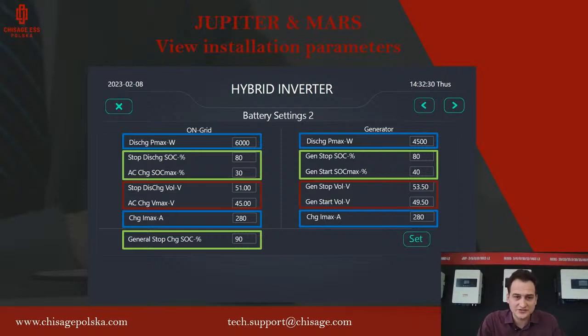General stop charge at the bottom is the maximum state of charge to which we want to charge our battery. Now it's 90, so the inverter will charge the battery to 90 and stop charging. Then if you need some power, it discharges to 80 and again charges to 90. So that's the setting here. And for the generator, same thing: again stop and again start. Those are the settings we have to fill when we want a signal for our genset.